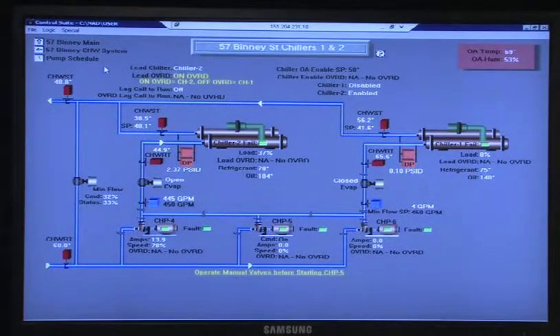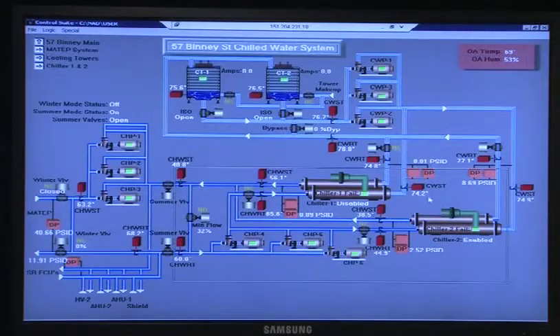Does that impede anything, or is it more of a wish list type of thing that we should do? What I'm saying is, you want to separate a condenser water loop and separate the chill water loops, showing it. You don't on that diagram. When you go back to the main chill water system, see how it looks like the water's coming in on the left side and coming out? That's how a bundle is made on the chiller, okay?